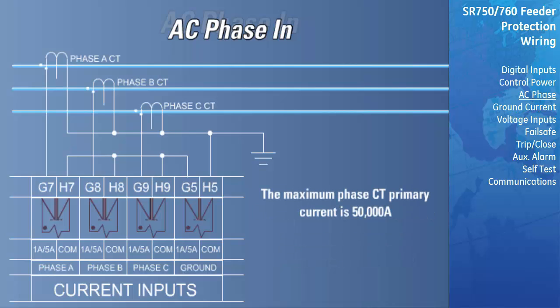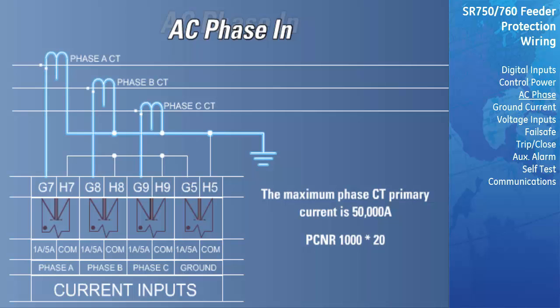The maximum phase CT primary current is 50,000 amps. The relay will measure correctly up to 20 times the phase current nominal rating. Since the conversion range is large, 1 amp or 5 amp CT secondaries must be specified at the time of order, such that the appropriate interposing CT may be installed in the unit. CTs chosen must be capable of driving the relay phase CT burden under maximum fault currents.